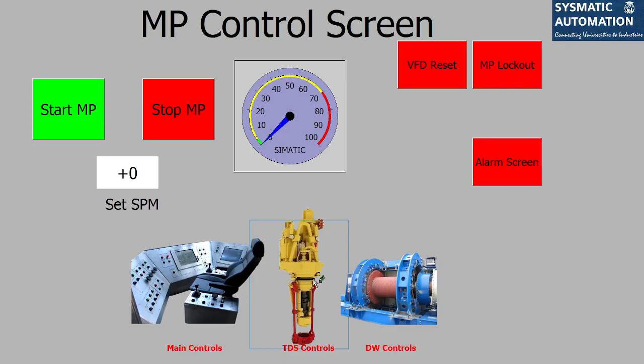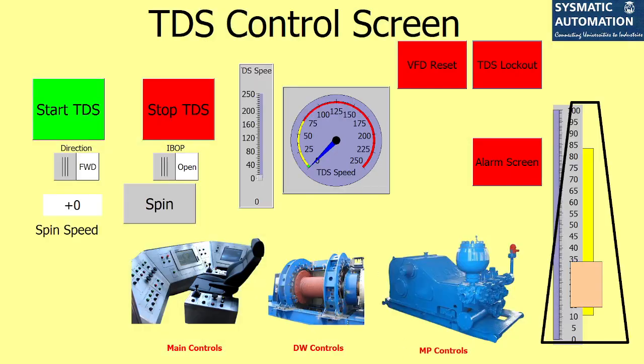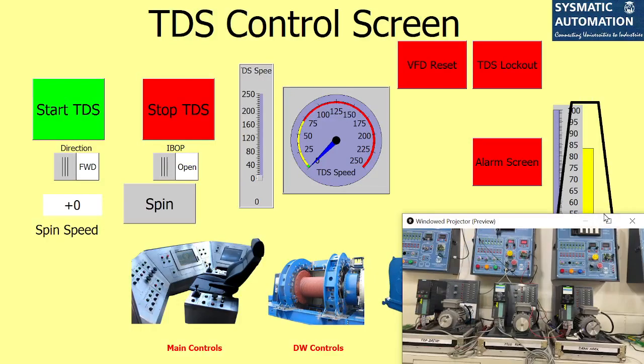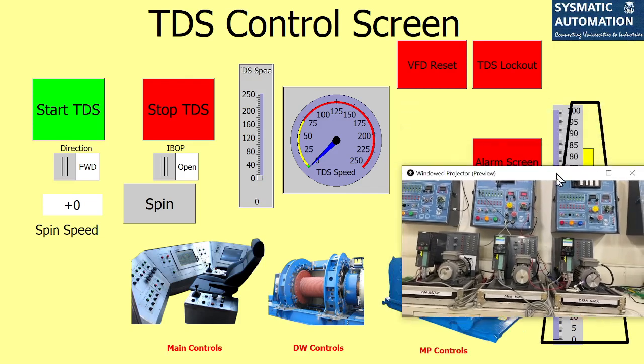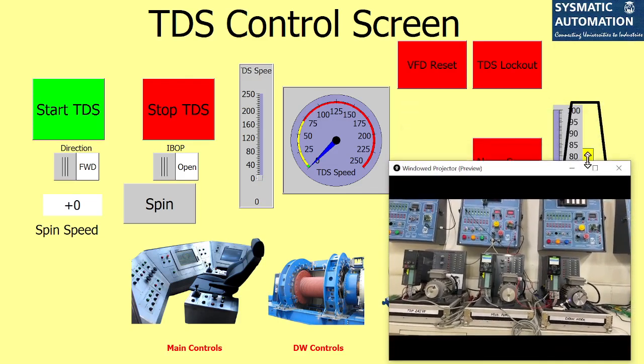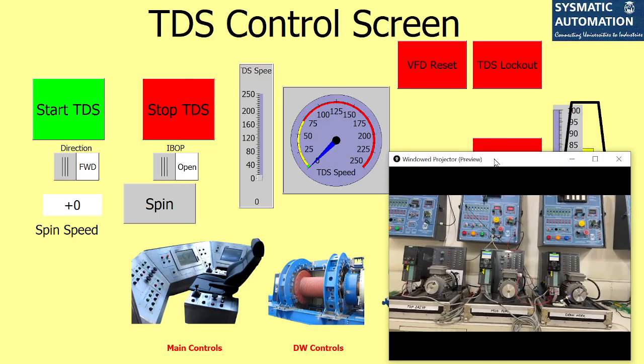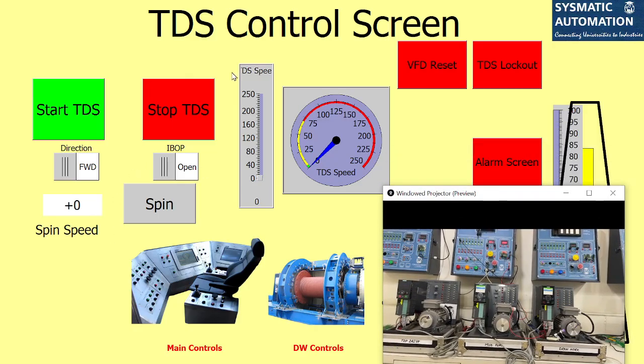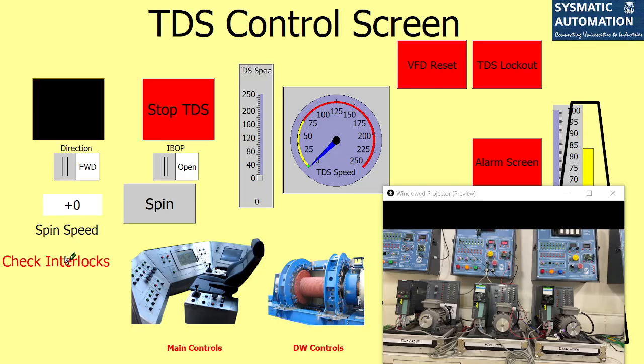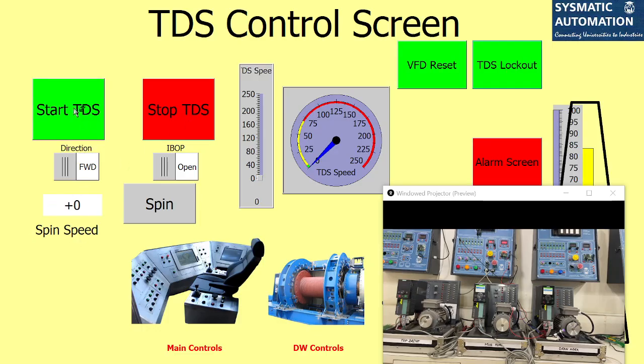Let's start with TDS controls. In the setup here, I will keep it on, so that you can see the operation of all the motors. Now, in top drive controls, if I try to start the top drive now, it won't let me start the top drive because it is asking me to check the interlock. The interlocks are the TDS lockout. If I remove the lockout, then I can start and stop the top drive.